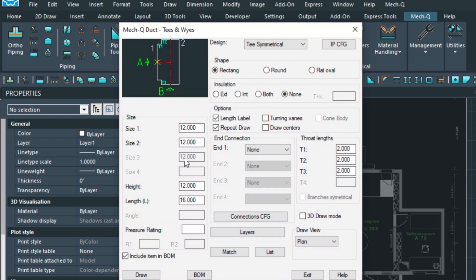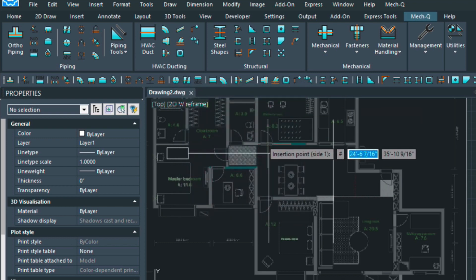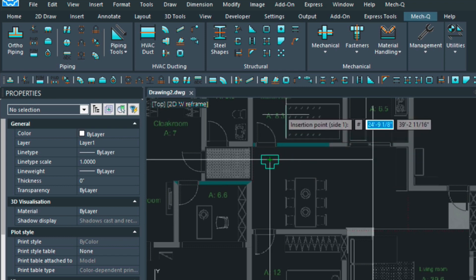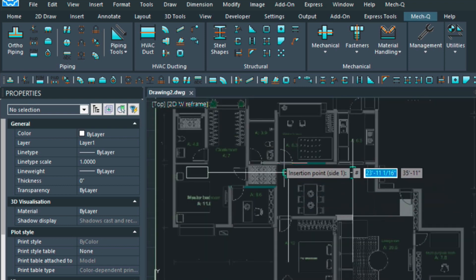We'll select the T — here we have a 12 by 12 by 12 T — and to define the throat lengths we'll come over to these boxes and make these all two inches. We're going to turn off the length label because we're not going to be annotating this, but make sure that repeat draw is turned on — it makes things easier. Then we're going to select Draw and pick the one for the center line. We'll put our first T here, rotating it around by moving our cursor. We can do the same with the second T, rotating it in, and then we're done with the T's.